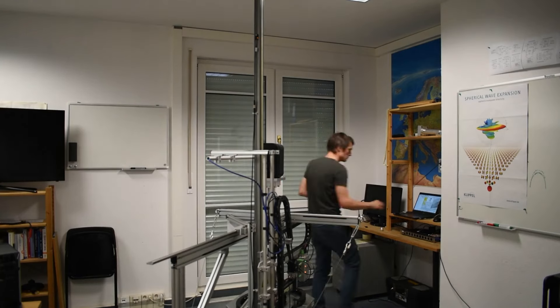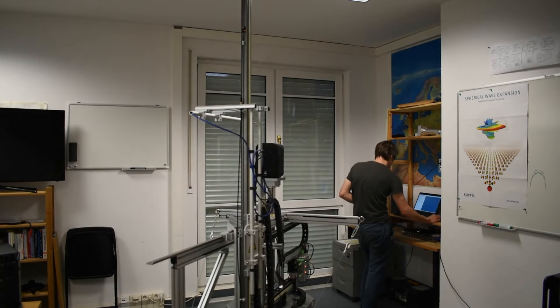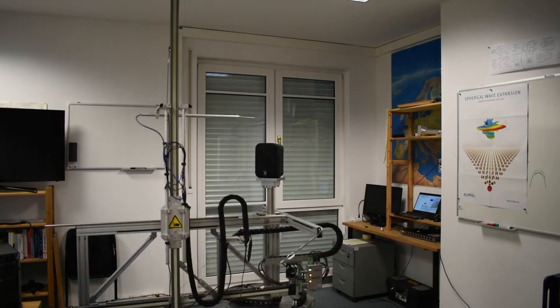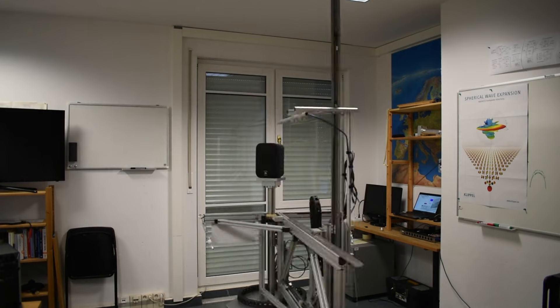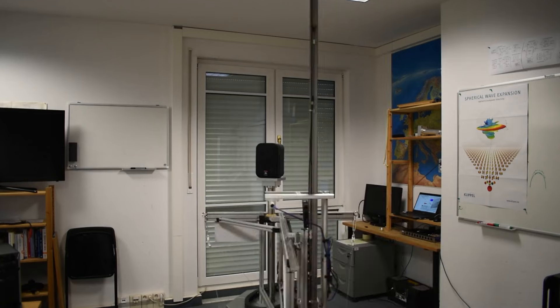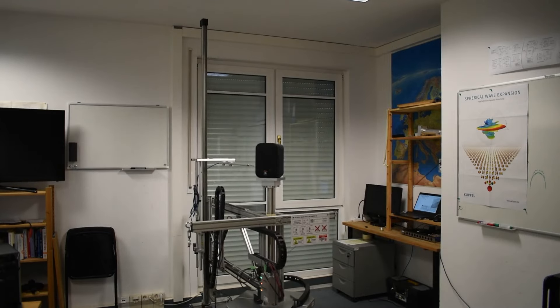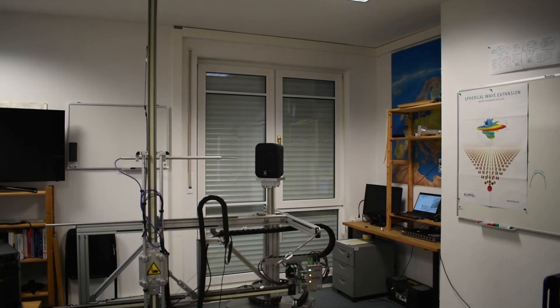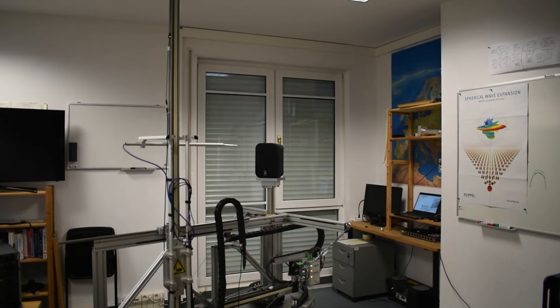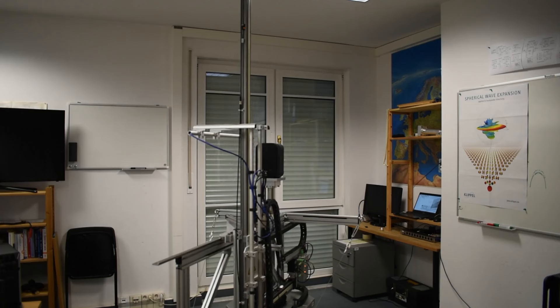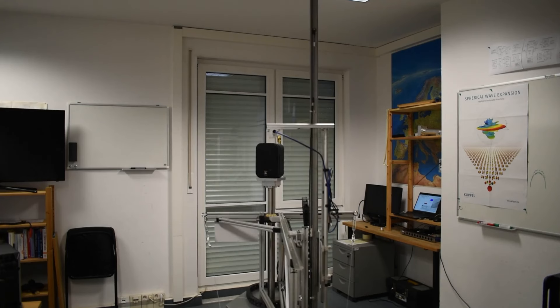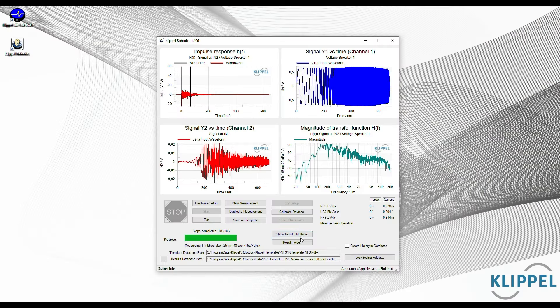Once the dimensions of the loudspeaker and the reference point are defined by moving the microphone to these positions, the robot is ready to start. Keeping in mind that the LFR method needs only the free-field response at low frequencies up to 1 kHz, we can benefit a lot from the holographic measurement approach. The sound field of such a speaker below 1 kHz is relatively simple and doesn't require a lot of points. That's why the NFS performs a rough scan with only 100 measurement points, which took about 15 minutes.